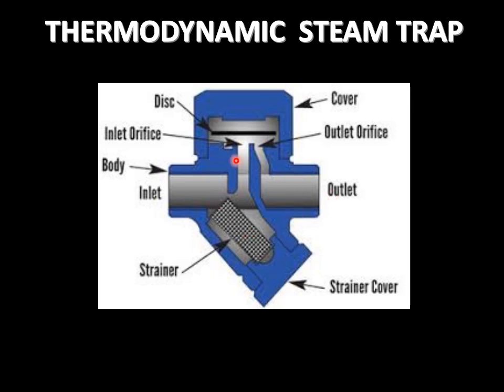When all the condensate is discharged to the outlet port, then the steam will begin to pass through this inlet orifice to the outlet orifice and will try to exit from this outlet port. But the speed of steam is far more than the condensate. So going by Bernoulli's principle, whenever there is an increase in velocity, there will be a sudden drop in pressure, and because of this pressure difference, the disk again moves back to its original position, thus closing the port and closing the connection between the inlet and the outlet orifice.